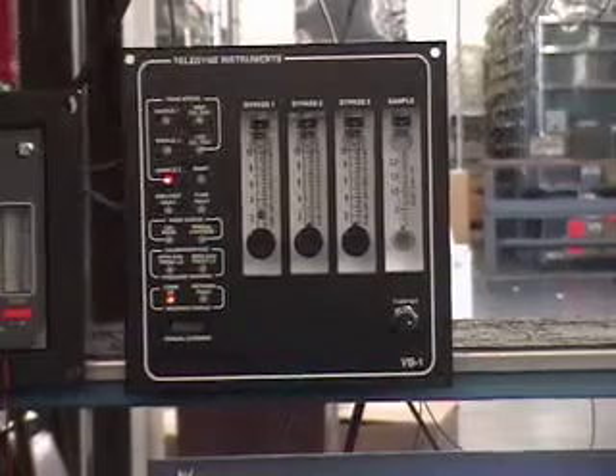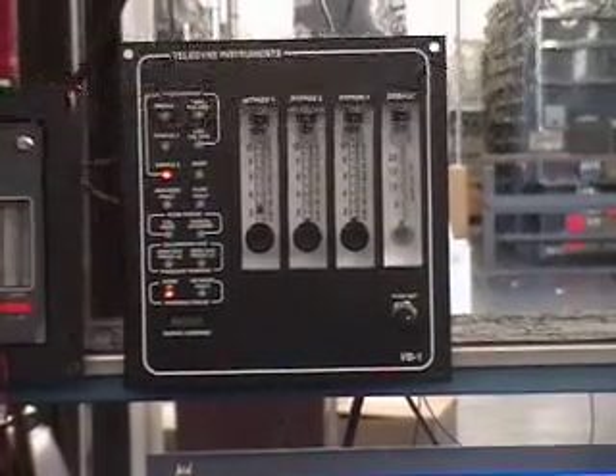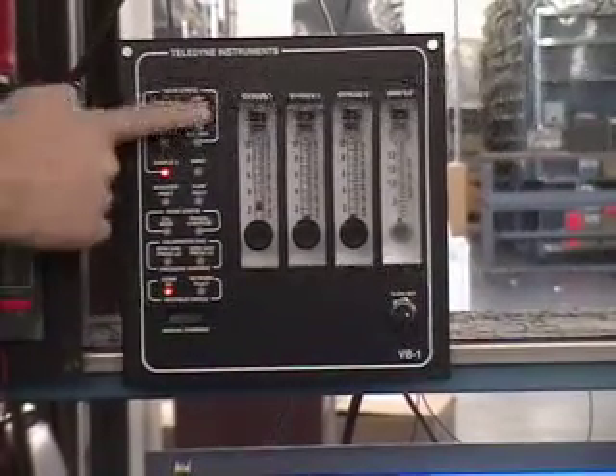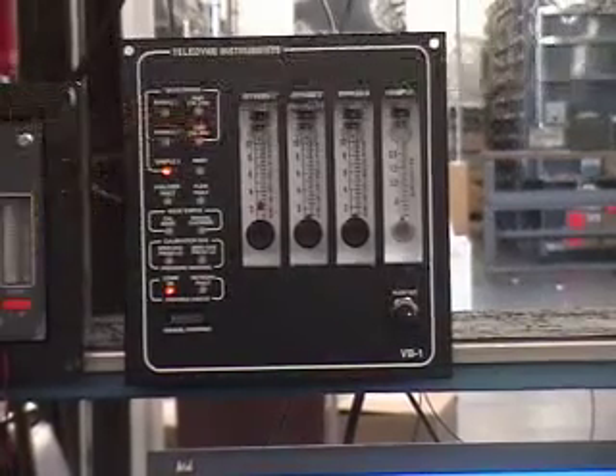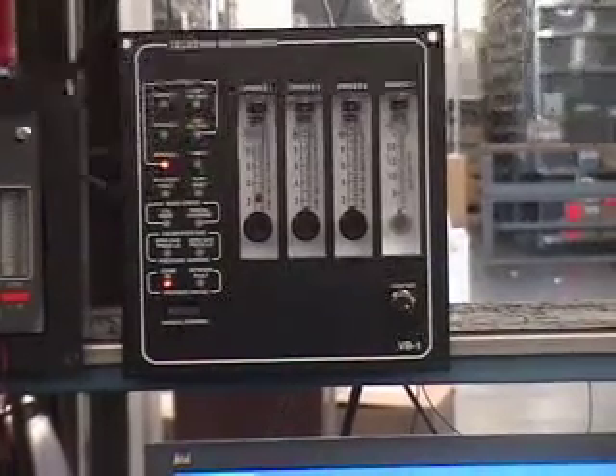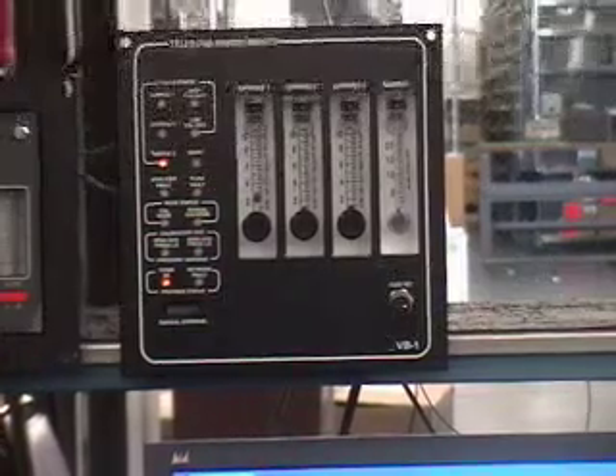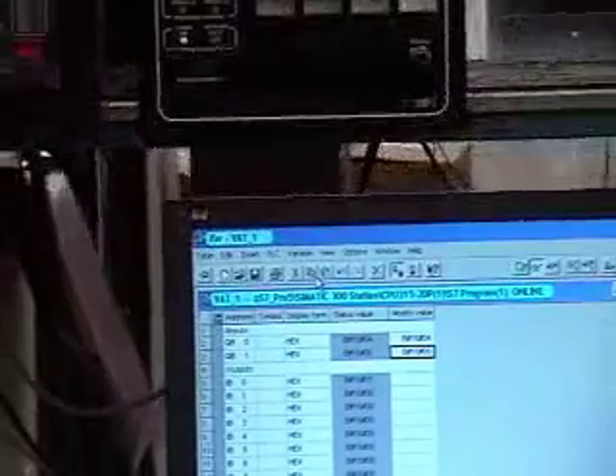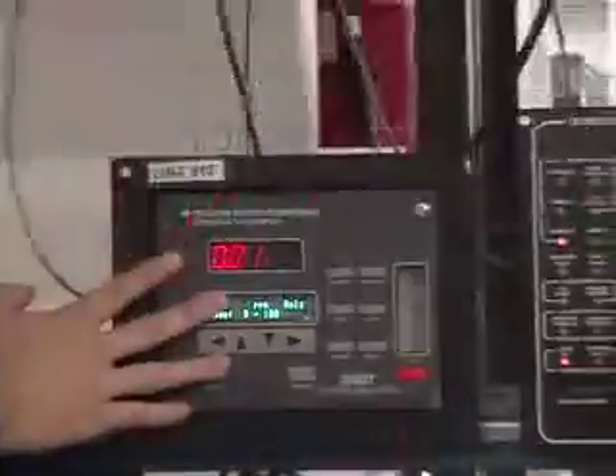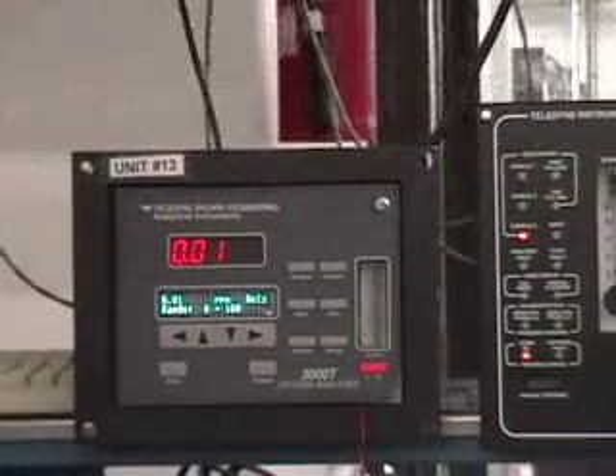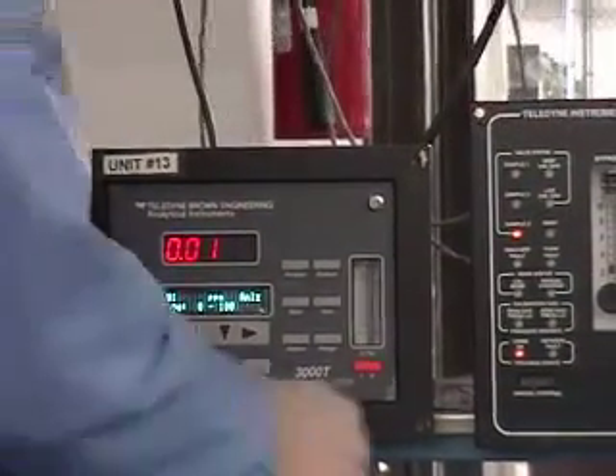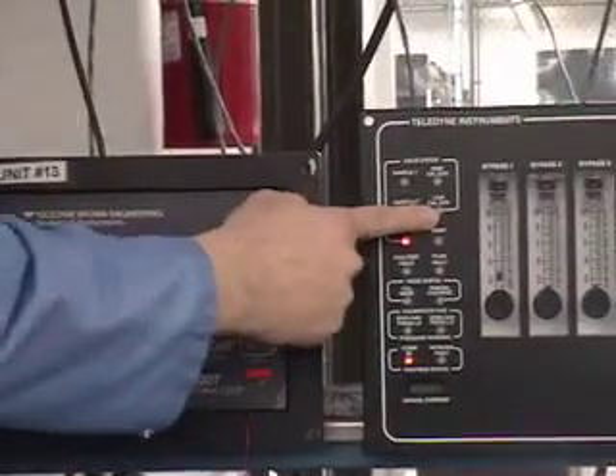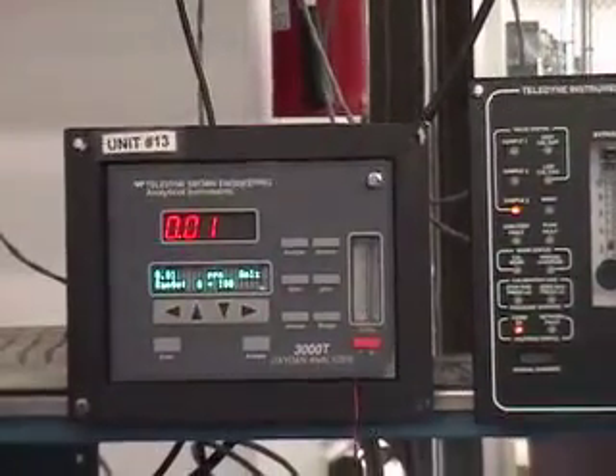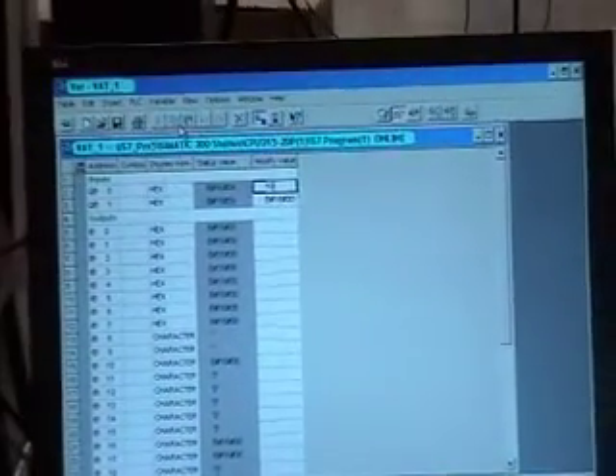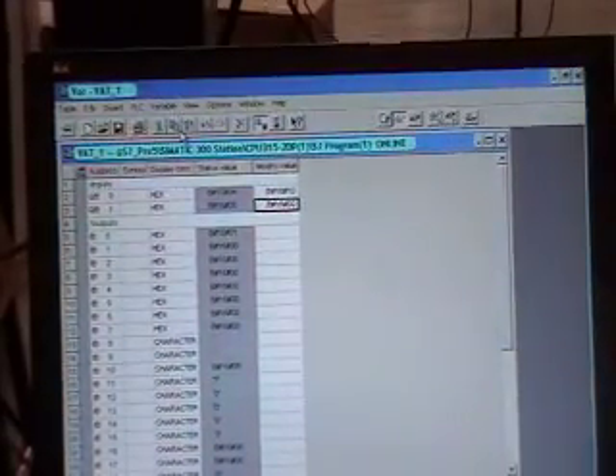Now we can go to the next one, which is to open up the 0 valve, which actually will send the instrument to a zero mode. So we have a cell simulator going into this analyzer to simulate inputs, sensor input. It's already close to 0, so we're going to send a 0 command first. The 0 command for this valve is 10. So I'm going to type 10. And I'm not sending it yet, just typed it in, but it's not sent.